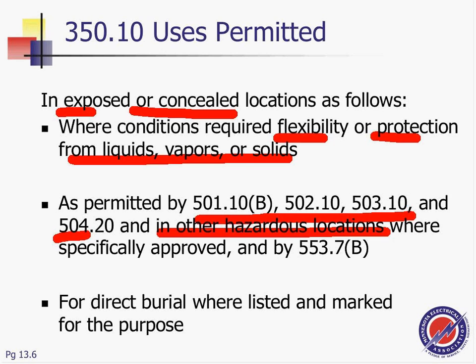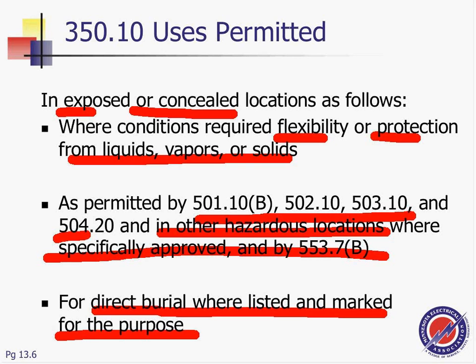You can also use it in a couple of hazardous locations where it's specified for that particular hazard, for flexibility. Now, can I direct bury it? No problem, where listed and marked for the purpose, you can go ahead and direct bury them. They're not meant to be direct buried. This is not the proper, the best installation for this conduit, but hey, no problem. They can be buried if needed.